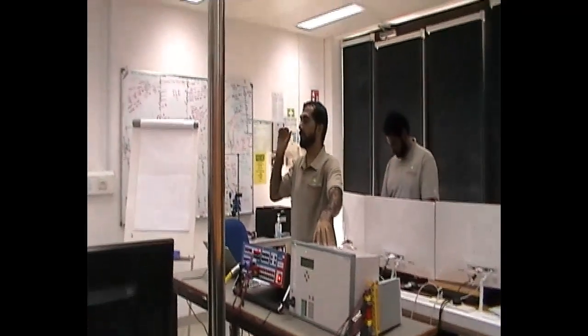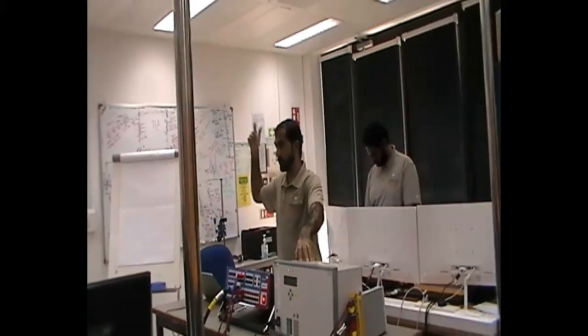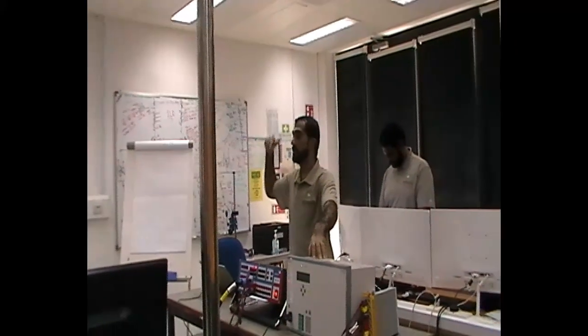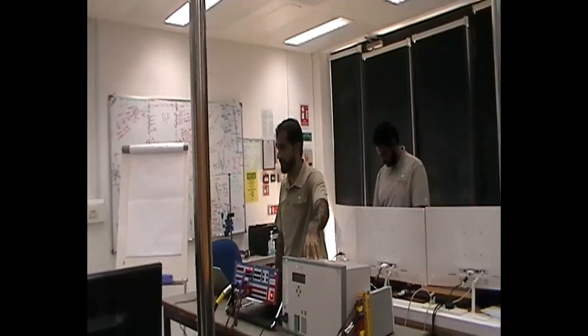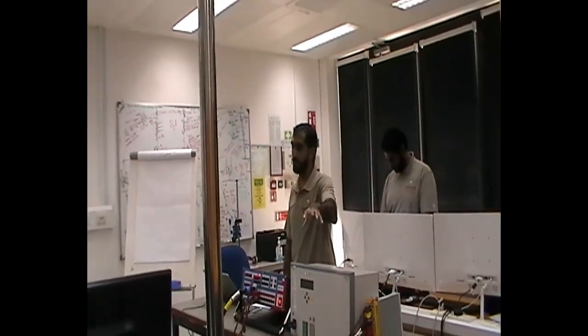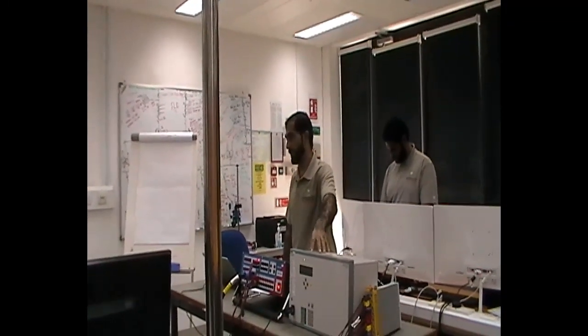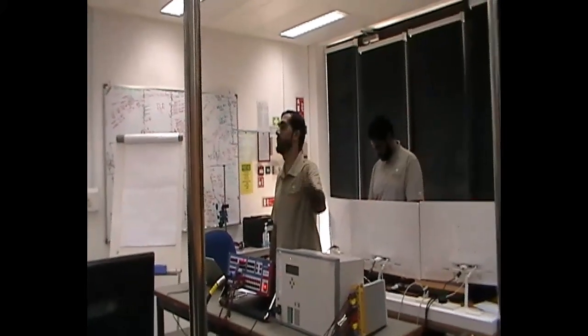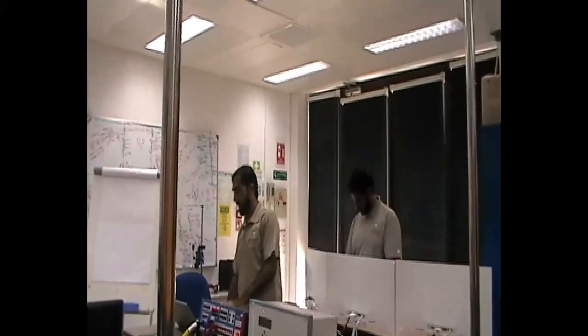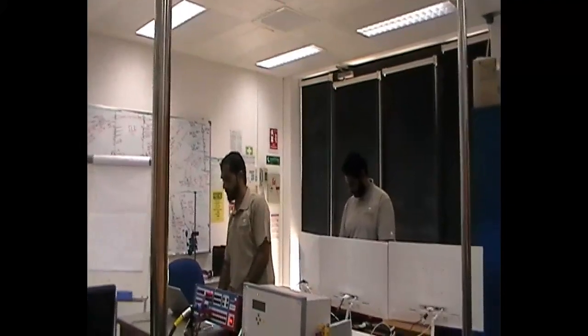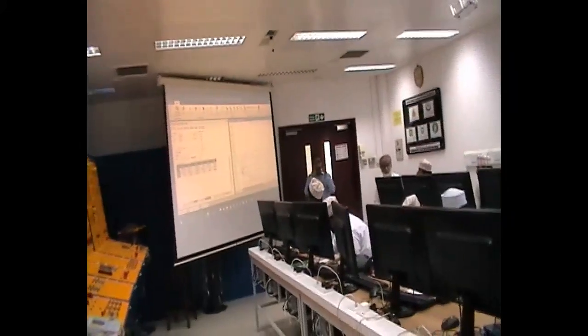It operates with different characteristics: zone 1, zone 2, zone 3. It's reaching different places in the line. This is the benefit of the distance relay, that I can enable different settings with different times. So, assume this is the line. You can see this one. This is my line, up to here. This is the end of my line.